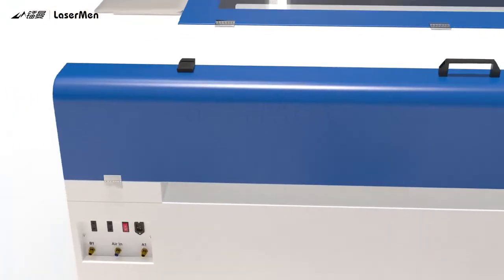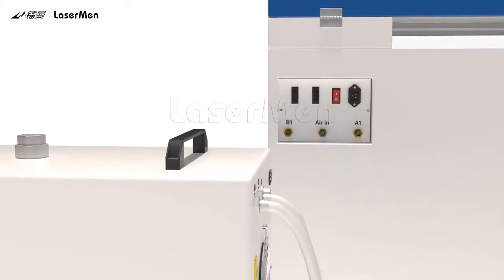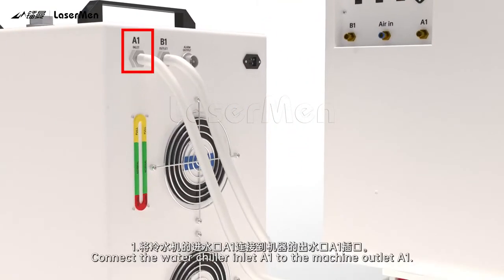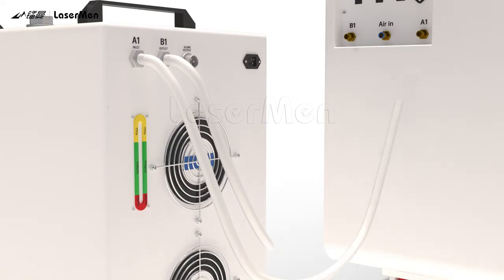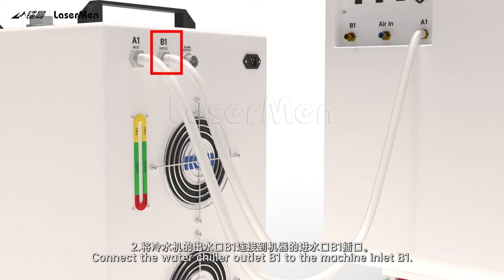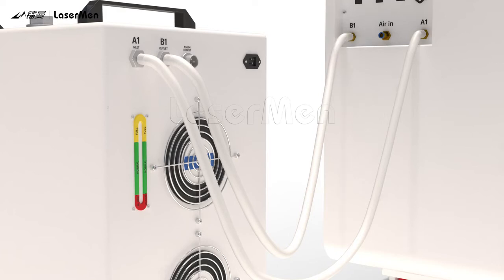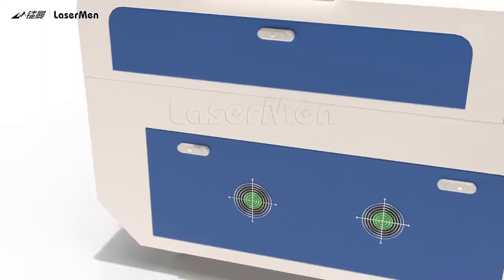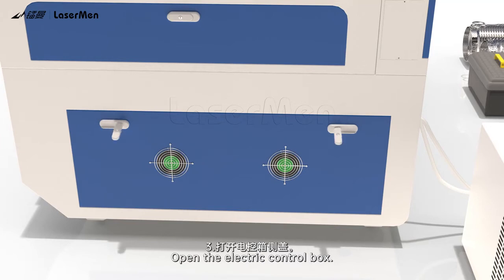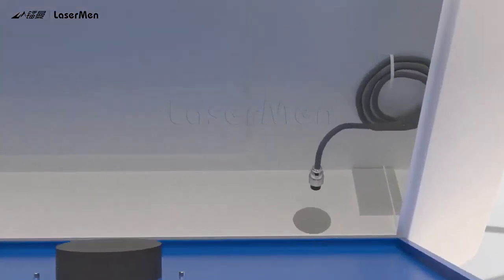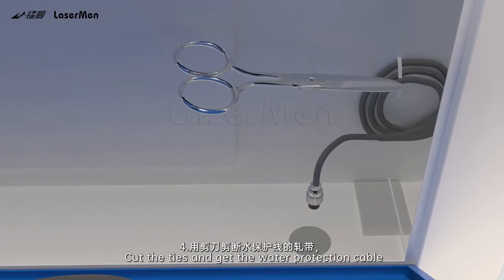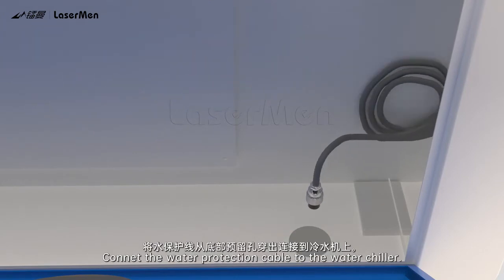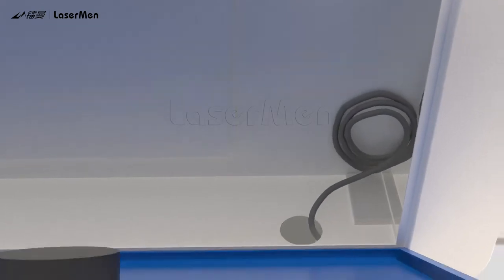Water chiller installation. 1. Connect the water chiller inlet A1 to the machine outlet A1. 2. Connect the water chiller outlet B1 to the machine inlet B1. 3. Open the electric control box. 4. Cut the ties and get the water protection cable. Connect the water protection cable to the water chiller.